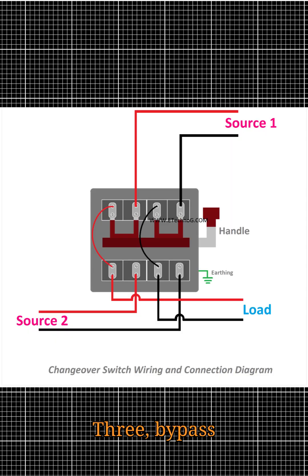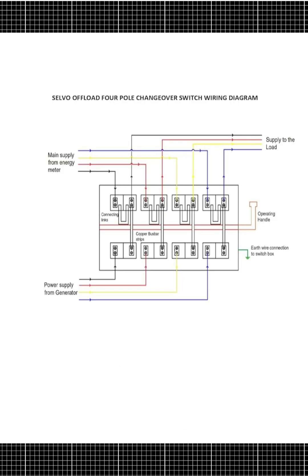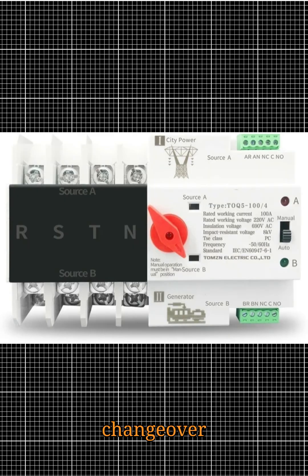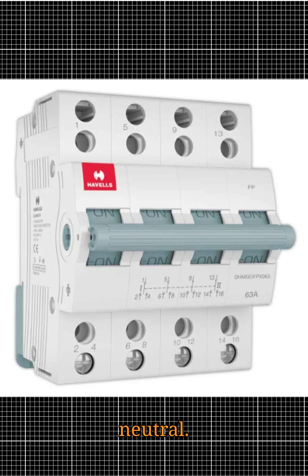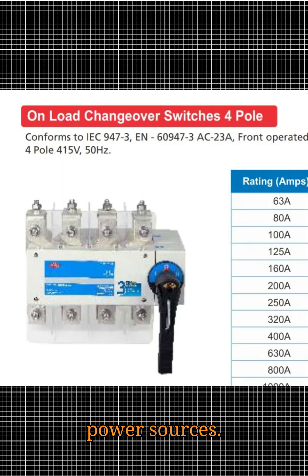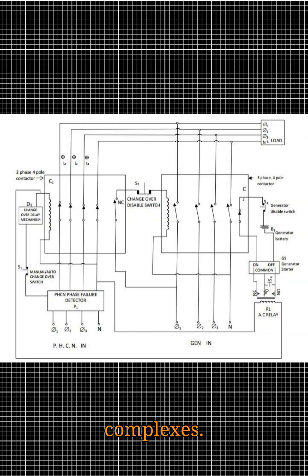3. Bypass changeover switch — used in critical applications such as factories and IT servers. Allows maintenance of the main changeover switch without interrupting the power supply. 4. Four-pole changeover switch — controls three-phase supply plus neutral, ensures complete isolation of power sources. Used in heavy industries and commercial complexes.